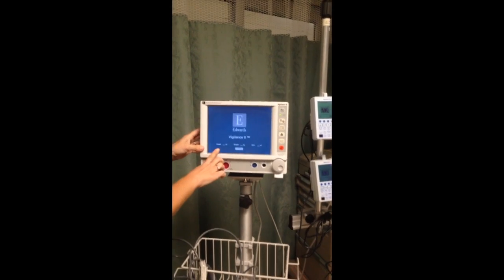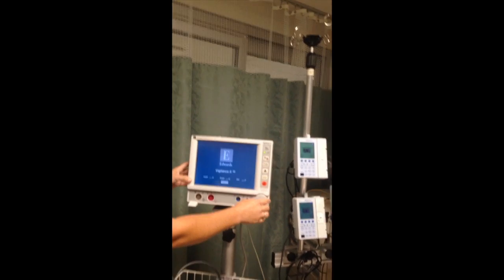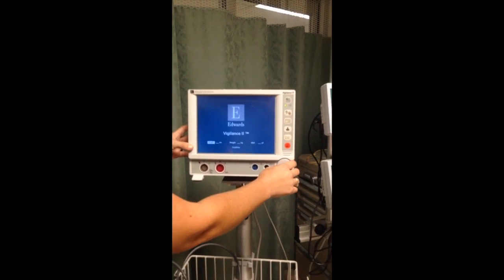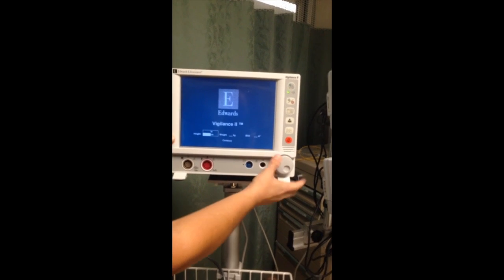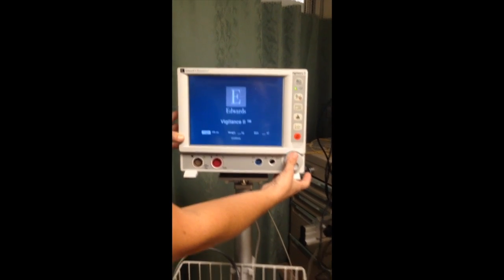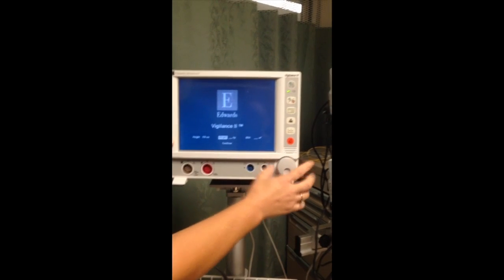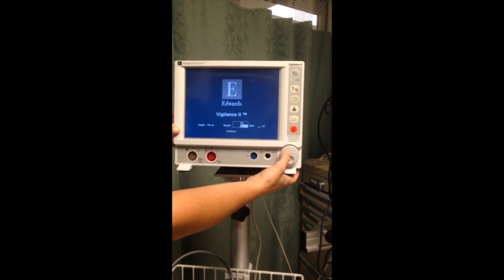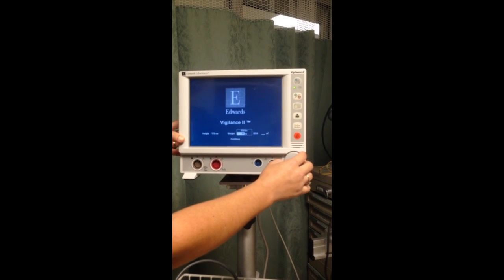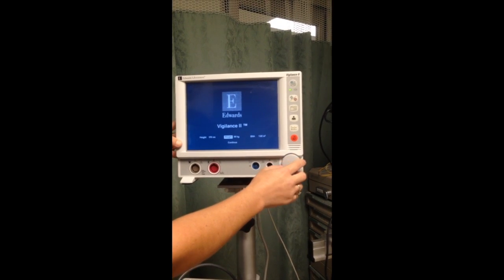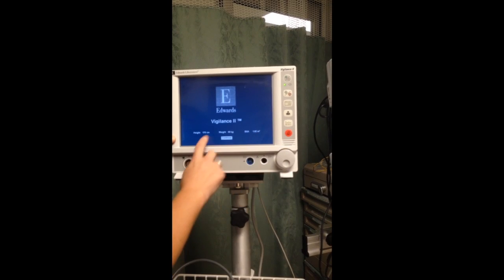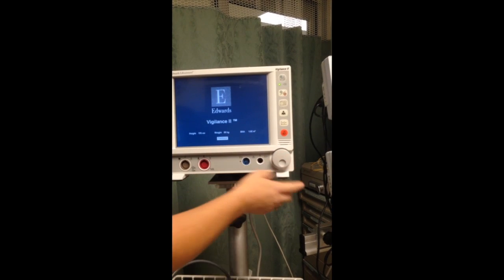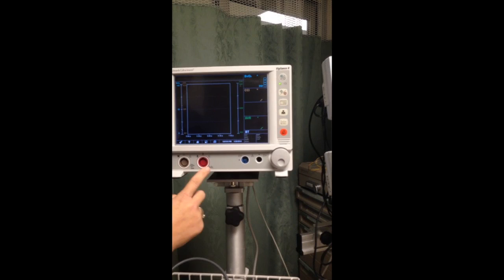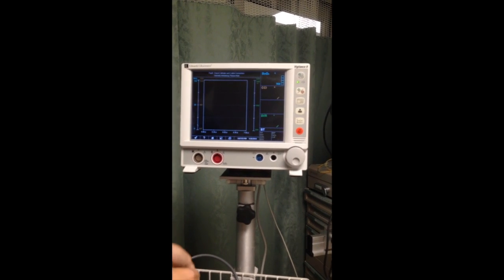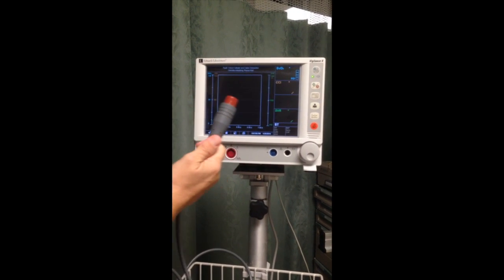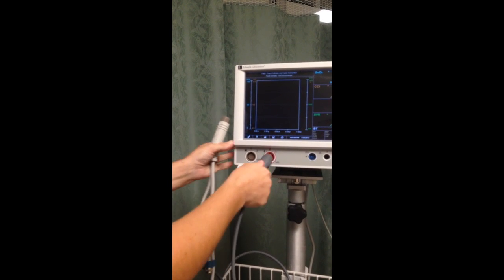The first step will be inputting your height and weight. So these are things you need to know prior to getting here. So our patient will put in centimeters is 170 centimeters. Scroll over to weight, click it once, click it for kilos, and 80 kilos. Click it again. It automatically does your BSA, so you continue to scroll until you get to continue and click again. At this point, you can insert your 2 cables, red to red, brown to brown.